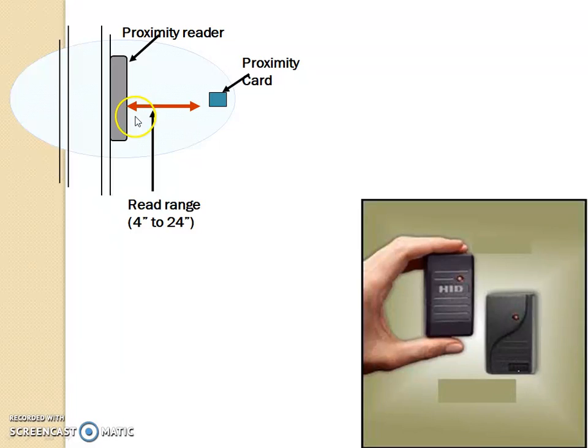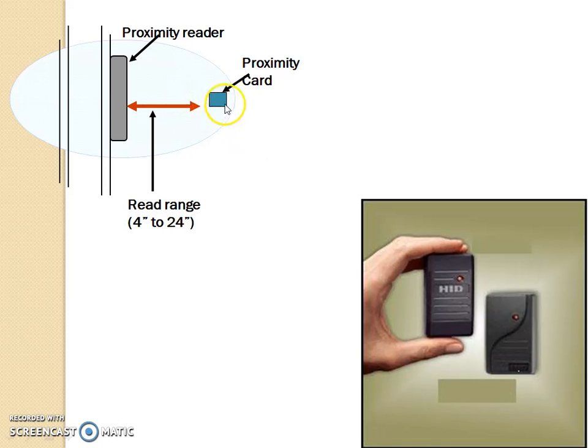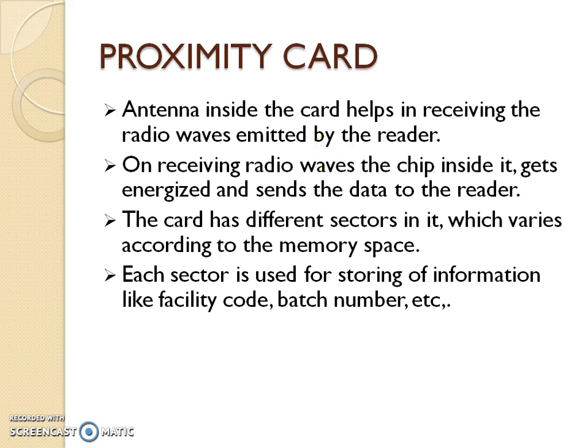In this sketch, we can see the proximity reader which is fixed or mounted on the wall. The proximity card is something which we bring near to the device — that is called the read range. In this particular image, the read range is 4 to 24 inches, roughly 2 feet. When the card comes within this 2 feet, the interaction happens between the card and the reader. Inside the proximity card, there is an antenna which helps in receiving the radio waves emitted by the reader. On receiving the radio waves, the chip inside gets energized and sends back the data to the reader.